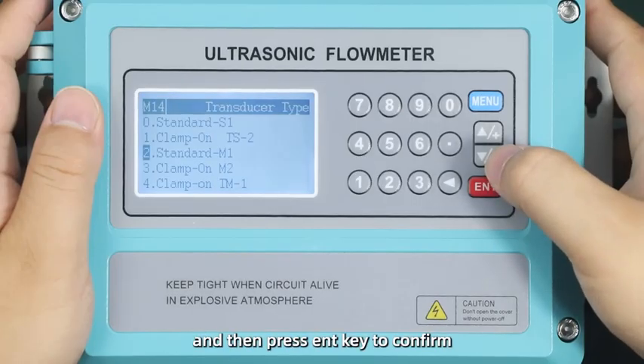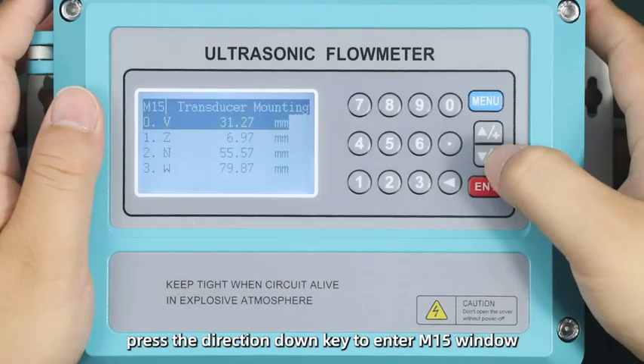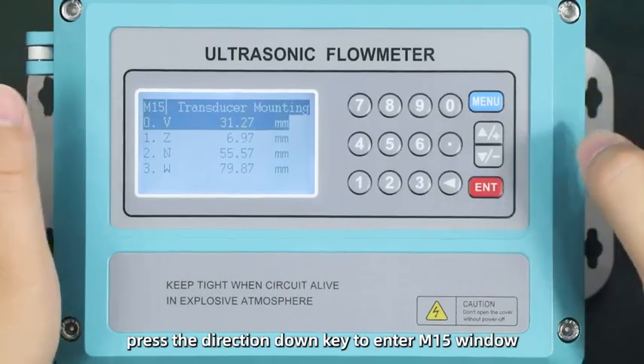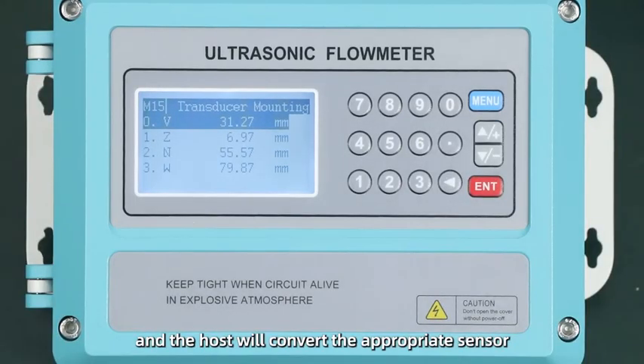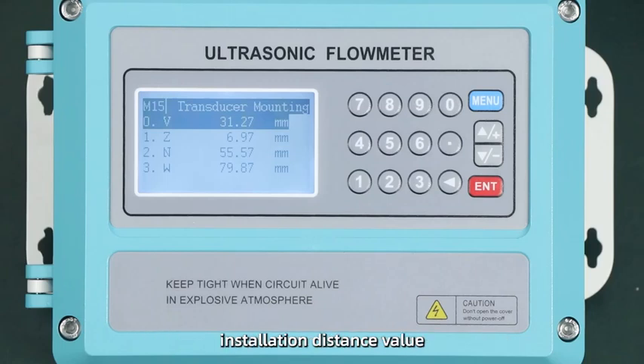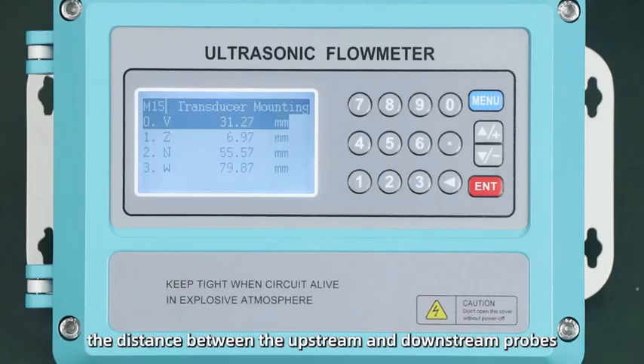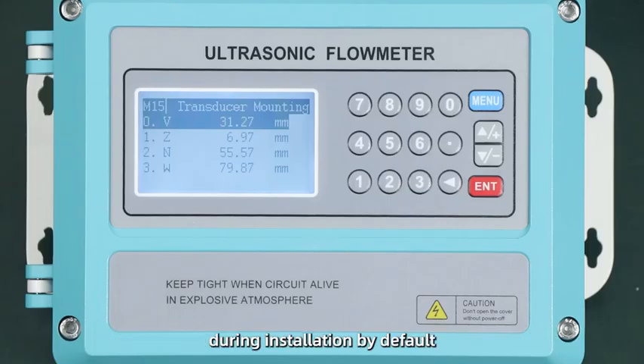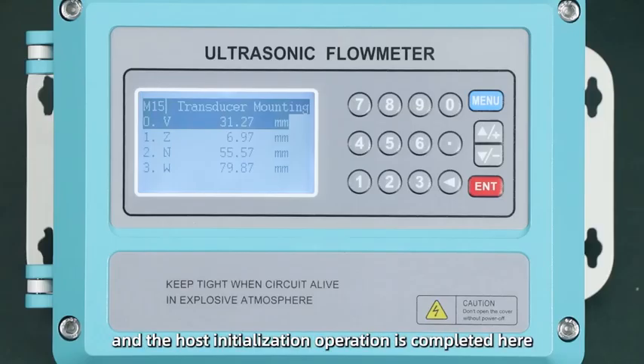key to confirm. Press the direction down key to enter M15 window, and the host will convert the appropriate sensor installation distance value under each installation mode according to the input parameters, which is the distance between the upstream and downstream probes during installation. By default, V method is selected for installation, and the host initialization operation is completed here.